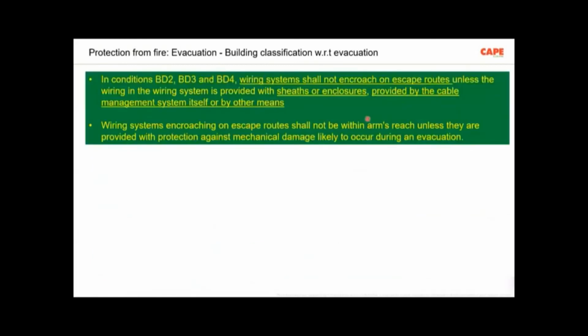Now, what do we require in this classification, BD2, BD3, and BD4? There are special requirements. You can go to clause number 4.2 of IS732, where these special requirements are very well documented. For example, in conditions BD2, BD3, BD4, wiring shall not encroach on escape routes unless the wiring system is provided with a sheath or enclosure provided by the cable management system itself or by other means. Basically, you cannot hang your wires in the escape route. You have to fix it properly, and you have to have special protective measures.